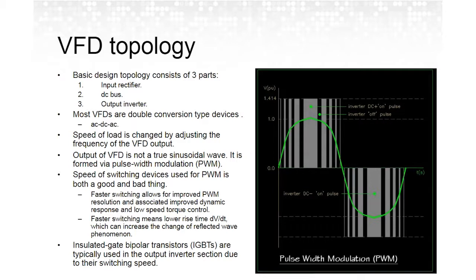Now, when we synthesize that waveform on the output of it, it's not a true sine wave. It's created by something called pulse width modulation. Basically what we're doing is we're taking that DC voltage, both a positive voltage and a negative voltage, and through pulse width modulation, divvying up that waveform into small chunks of equal amplitude but different time. And as a result, the average amount of power that we see is represented by the curve that you see there.